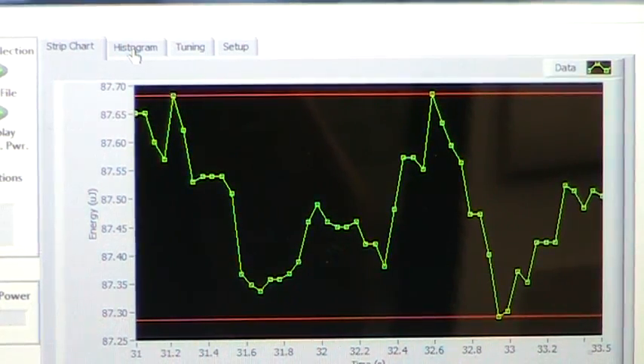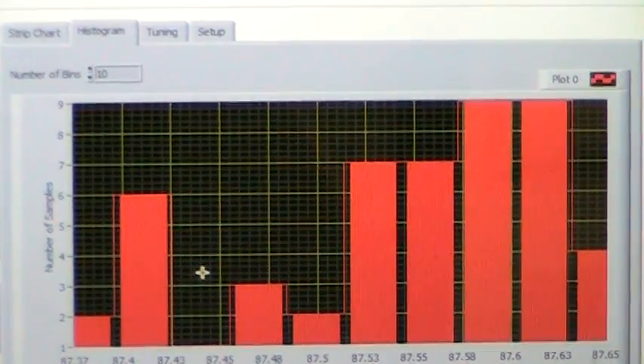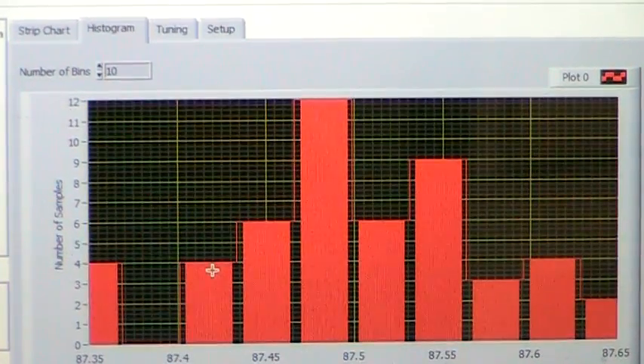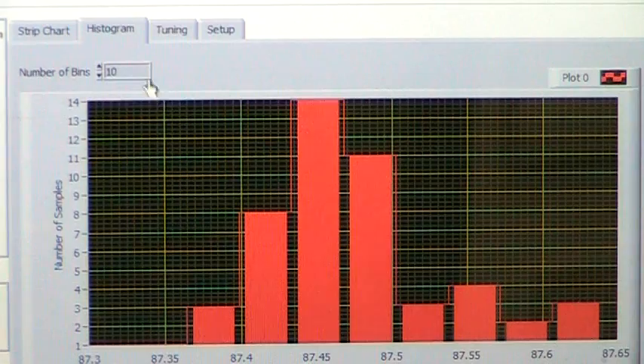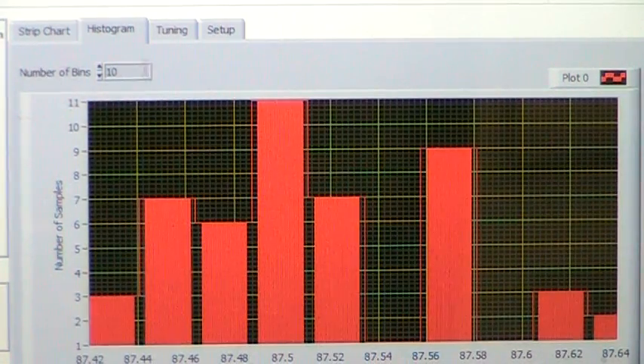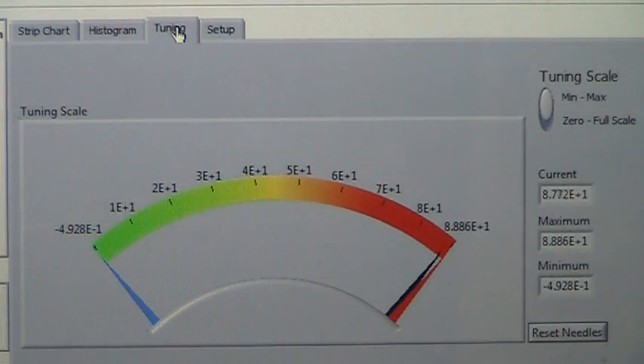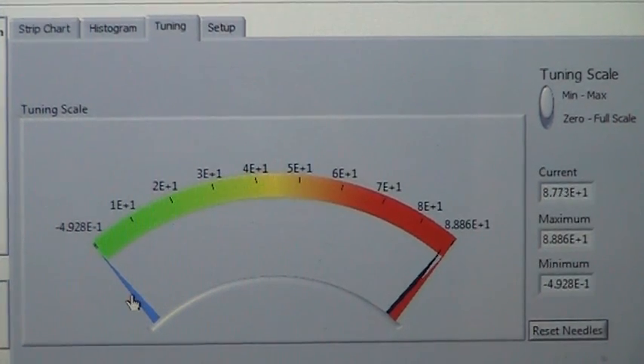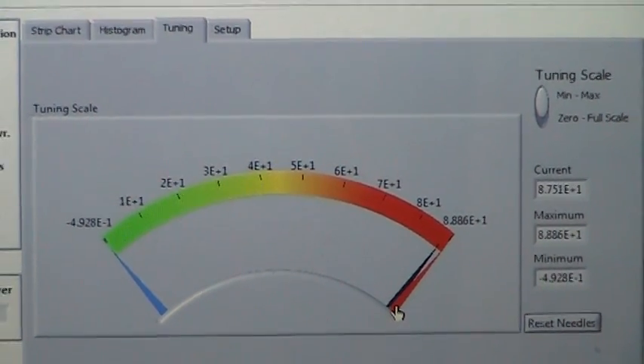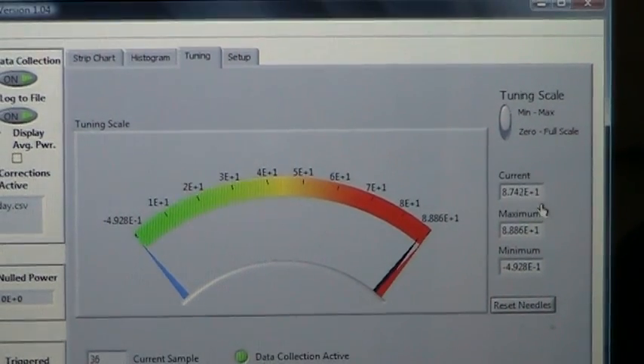The next screen is a histogram. In this screen we're showing the data in pulse energy in bins. The user can actually set the bin size using this box up here. Next is the tuning mode. This is a convenient analog tuning screen that allows you to tune the laser or peak your laser when you're setting things up. Here I'm putting an ND filter in the laser beam. You can see the readings changing and you can see the needle moving back and forth very rapidly. The blue needle is the minimum reading, the red needle is the maximum reading. And the actual readings are displayed to the side here.